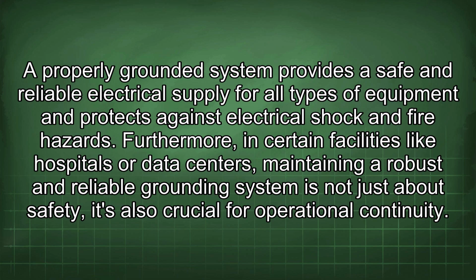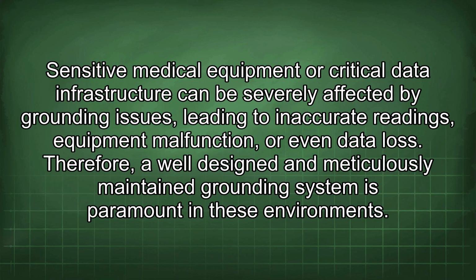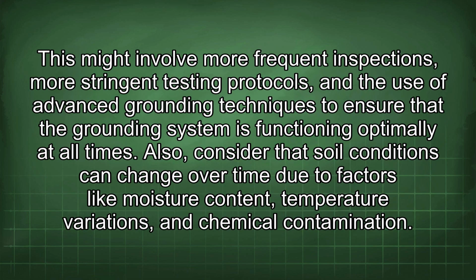Furthermore, in certain facilities like hospitals or data centers, maintaining a robust and reliable grounding system is not just about safety, it's also crucial for operational continuity. Sensitive medical equipment or critical data infrastructure can be severely affected by grounding issues, leading to inaccurate readings, equipment malfunction, or even data loss. Therefore, a well-designed and meticulously maintained grounding system is paramount in these environments. This might involve more frequent inspections, more stringent testing protocols, and the use of advanced grounding techniques to ensure that the grounding system is functioning optimally at all times.